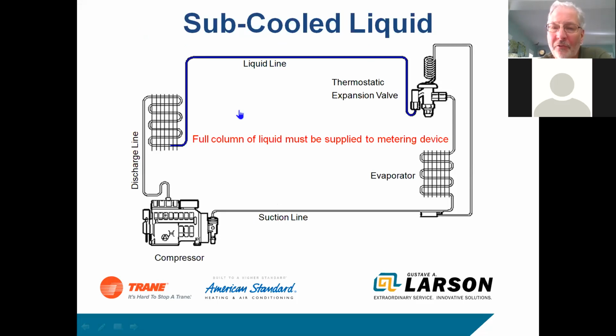If you put a sight glass in a system right here, all that tells you is you have liquid leaving the condenser. It really has no effect on whether you're charged properly or not. So if you're going to put a sight glass in, it needs to be in front of the expansion valve in order to let you know you do have liquid hitting that valve. But you still have no idea how much liquid, because if I have 10 degrees of subcool, I'm flashing from a gas to a liquid somewhere around here, and I'm sending liquid to the valve. If I've got 20 degrees of subcool, now I'm flashing into a liquid somewhere halfway in here. If I've got 30 degrees, I might have a flooded condenser.